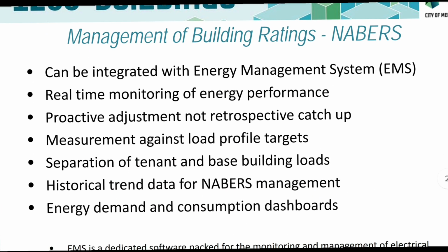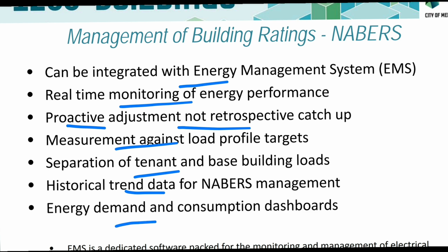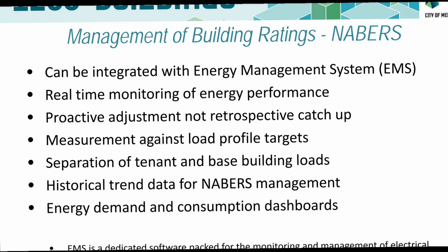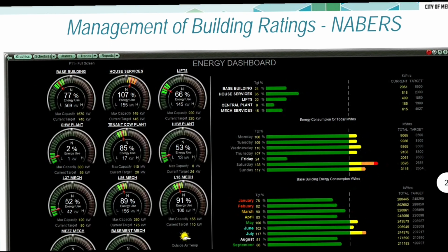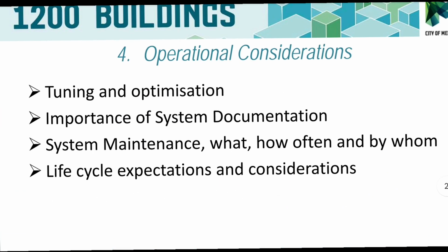Okay, next is management of building ratings. NABERS can be integrated with the energy management system, EMS: real-time monitoring of energy performance, proactive adjustment, not retrospective catch-up, measurement against load profile targets, separation of tenant and base building loads, historical trend data for NABERS management, energy demand and consumption dashboards. Okay, all you need is a BMS for management of building rating, NABERS.